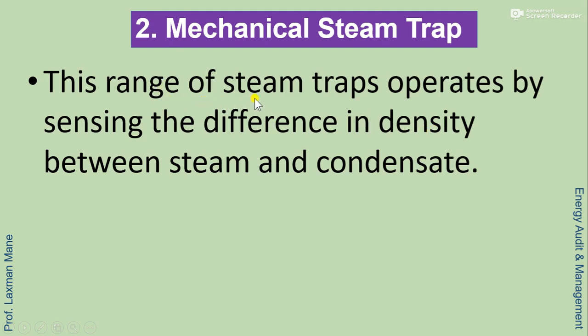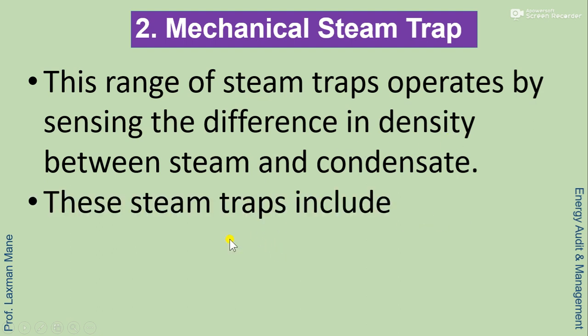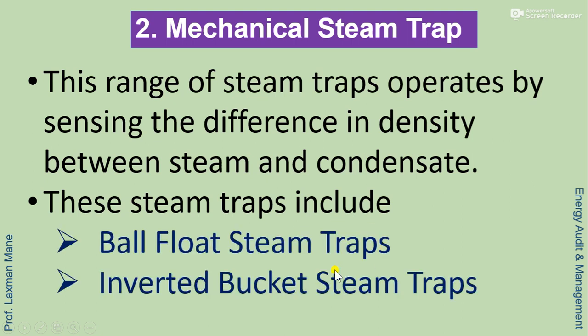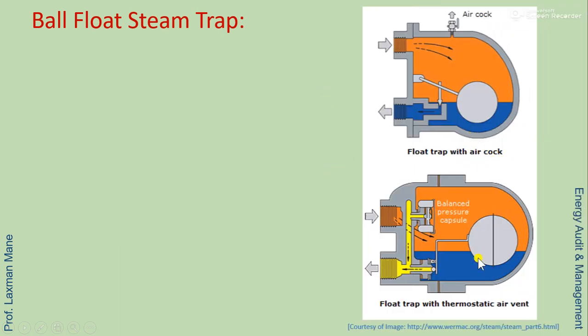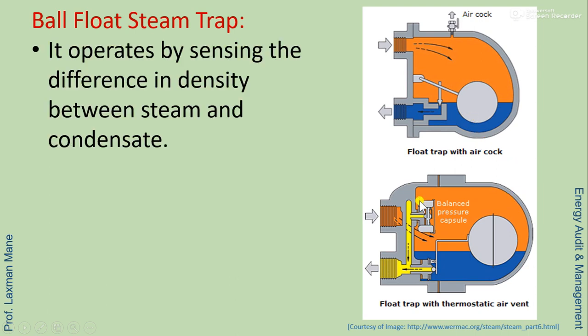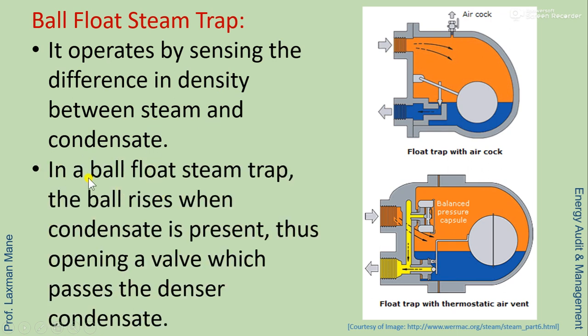The second major type is the mechanical steam trap. This range of steam trap operates by sensing the difference in density between steam and condensate. Mechanical steam traps include two types: ball float steam traps and inverted bucket steam traps. In the ball float steam trap, the ball rises when condensate is present, opening a valve which passes the denser condensate.